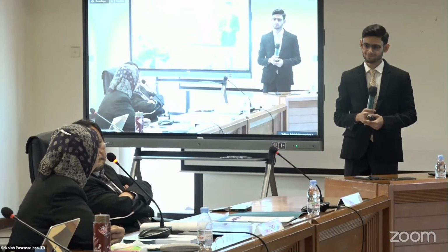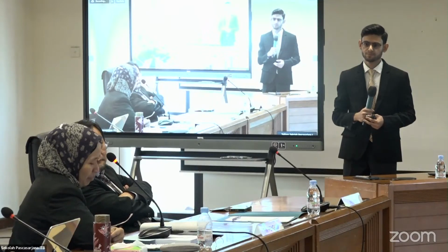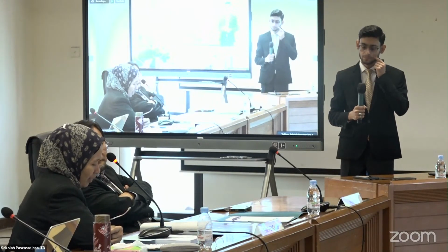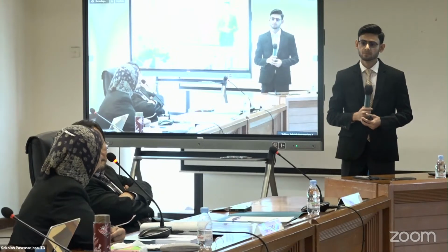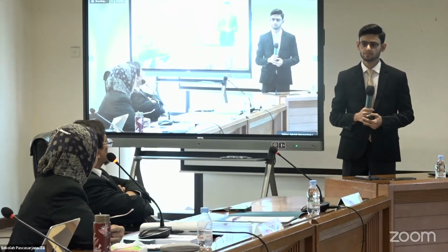you also claim that the safe way to operate the hollow fiber membrane bioreactor is below critical flux. Yes. But apparently this critical flux is very low. Even if you already increase to, let's say, median flux, it's only about 14.7 liter per meter square per hour. So what will be the suggestion to improve the performance and overcome this problem? Because I think the volume of the wastewater is very high compared to this flux.